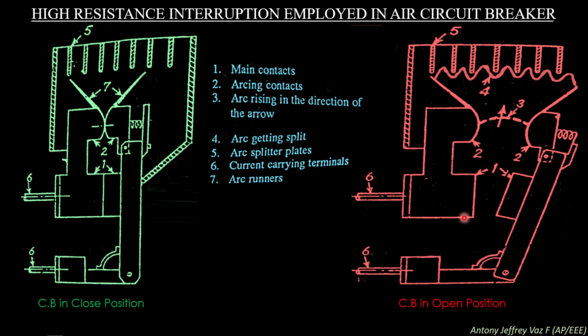And this is the same circuit breaker in open position. Now the two main contacts are separated. At the same time, the arcing contacts also get separated. In that time, the arc starts to ignite in the arcing contact in the third position.